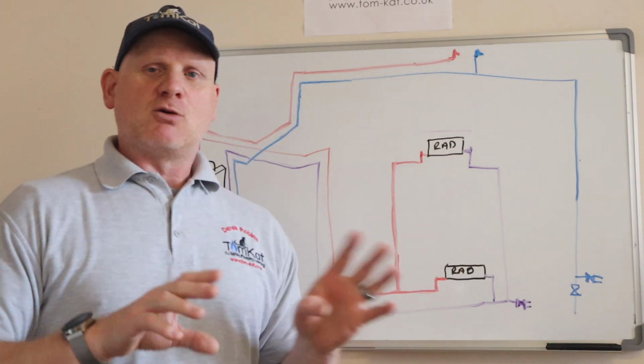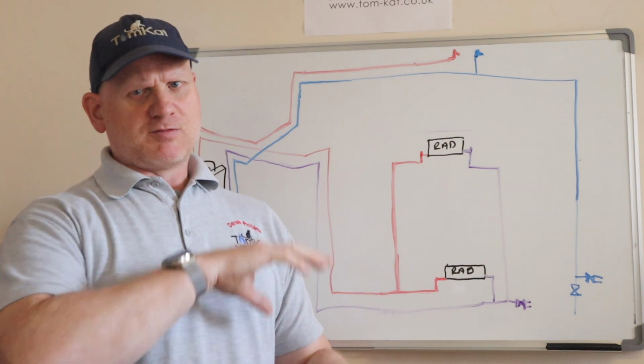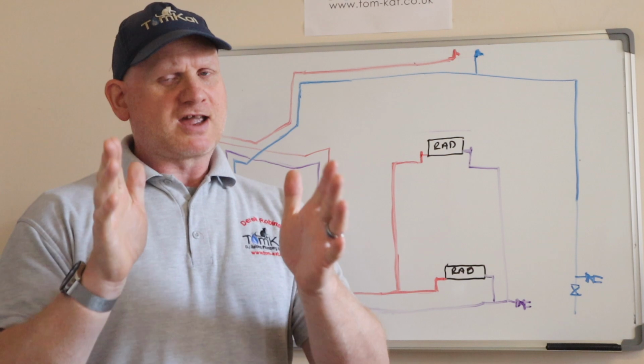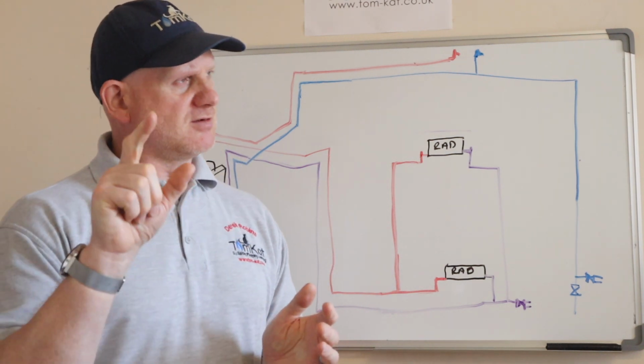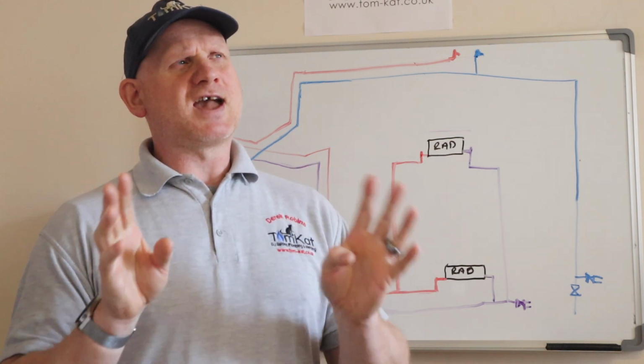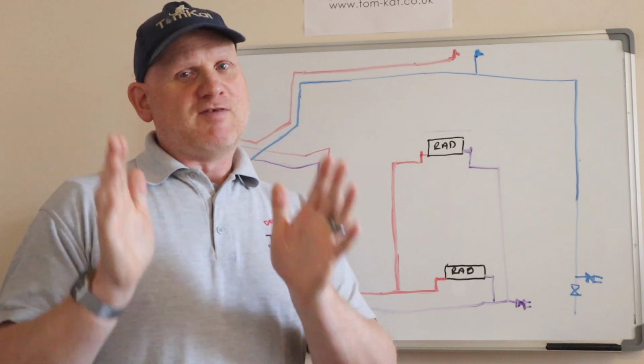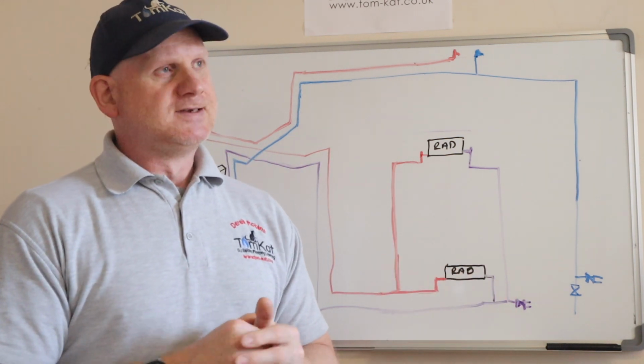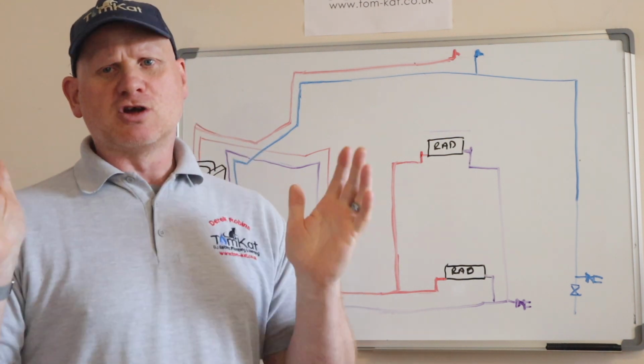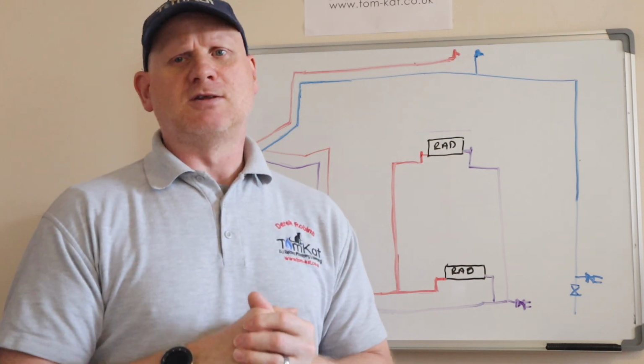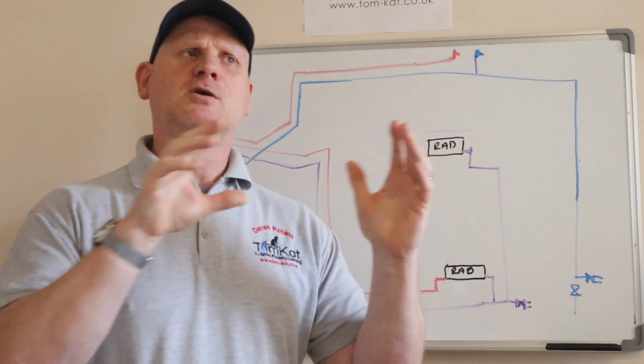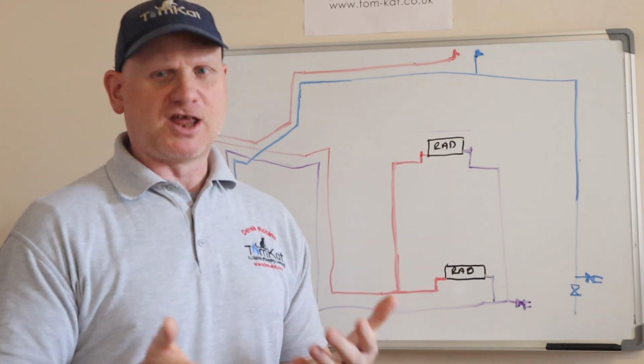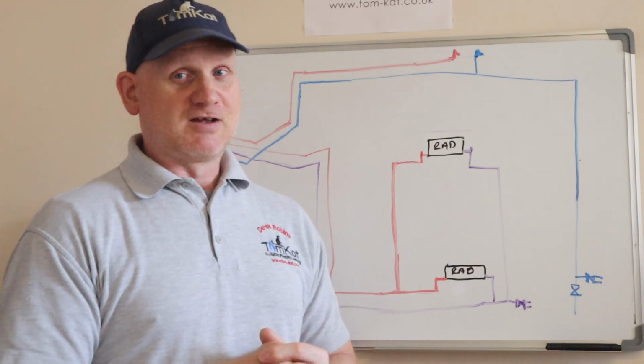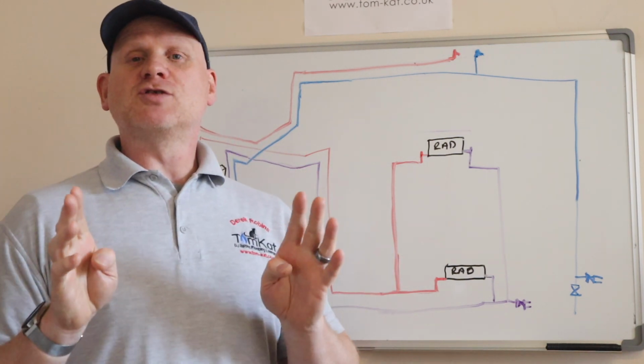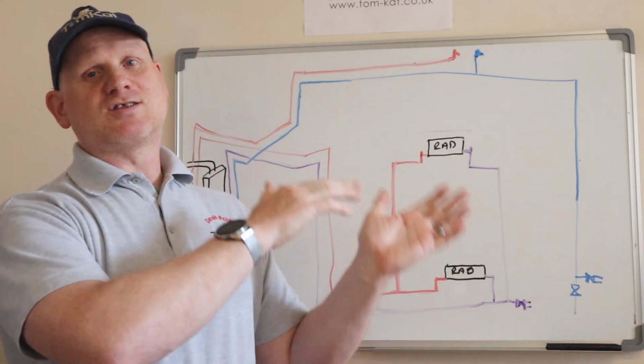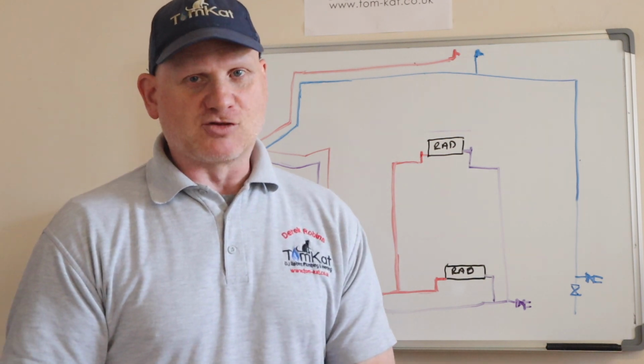Now, a couple of things there. First of all, if you are going from gravity hot water to pump central heating, always check and make sure there's no anti-gravity valve. You'll need to remove it. And also, you've got to kind of be aware of changing it from vented to sealed has its own problems. It will find any leaks you've got. And also, because we've got to flush and clean the systems out, that also can create leaks as well. So these are all the things you have to relay to the customer when you're changing these really old systems over. They do need flushing and cleaning out. So if you want to see how to change a vented system to a sealed system, then we've got a video for that as well.